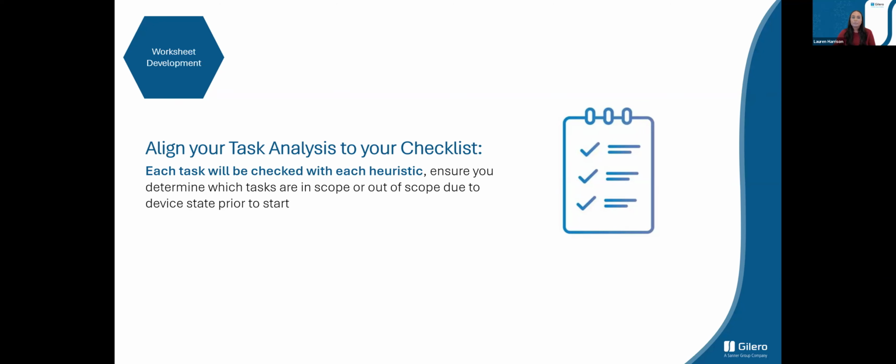to an IFU. If you do want to evaluate the IFU as well, you can do this as a separate analysis specifically for the IFU. Keeping both the device and the IFU separate is your most ideal option because it allows researchers to optimize their heuristic list for the user interface.